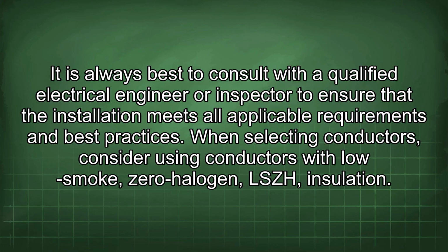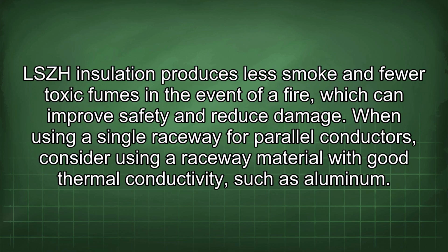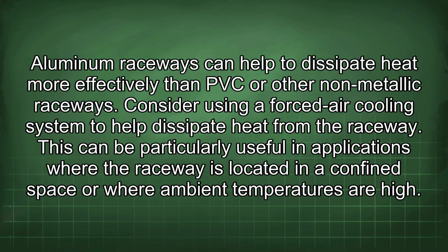When selecting conductors, consider using conductors with low smoke, zero halogen (LSZH) insulation. LSZH insulation produces less smoke and fewer toxic fumes in the event of a fire, which can improve safety and reduce damage. When using a single raceway for parallel conductors, consider using a raceway material with good thermal conductivity, such as aluminum. Aluminum raceways can help to dissipate heat more effectively than PVC or other non-metallic raceways. Consider using a forced air cooling system to help dissipate heat from the raceway. This can be particularly useful in applications where the raceway is located in a confined space or where ambient temperatures are high.